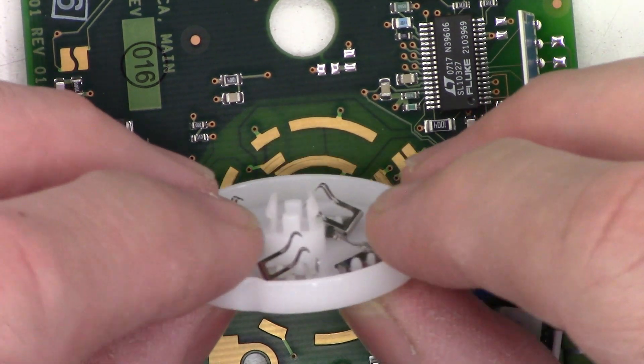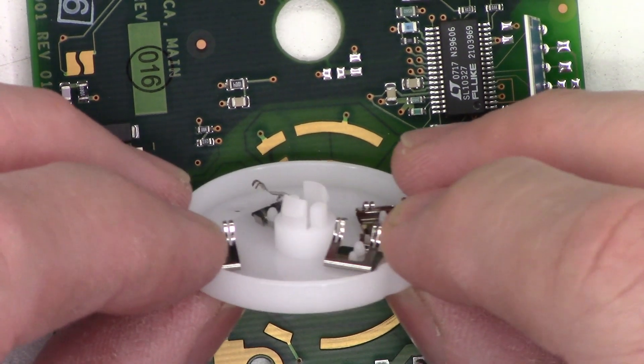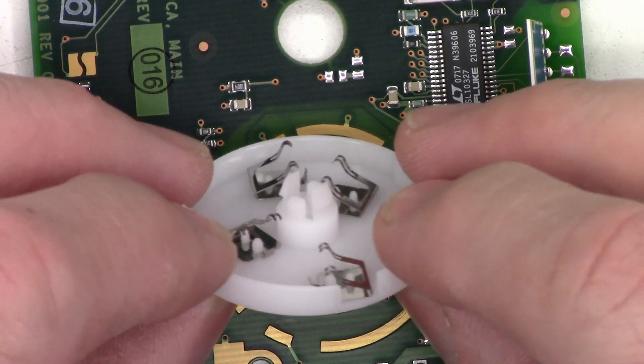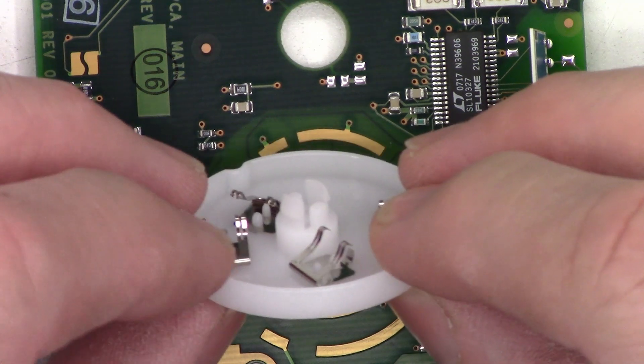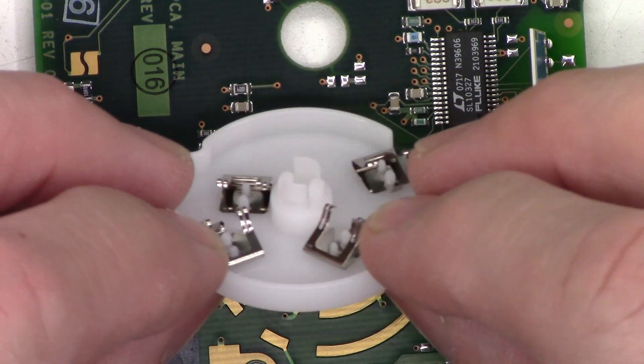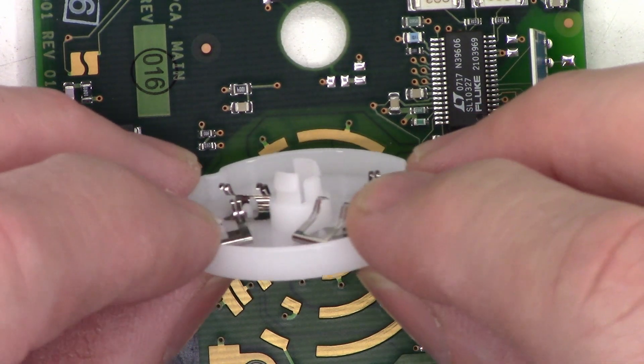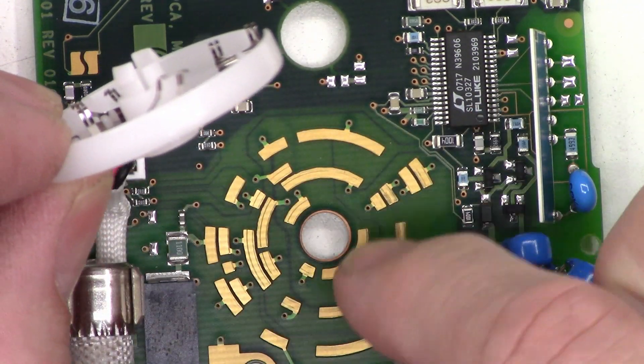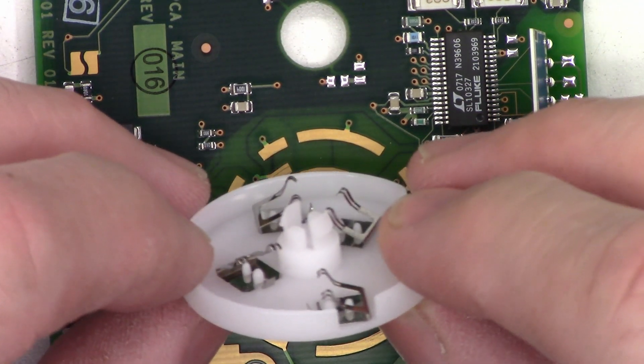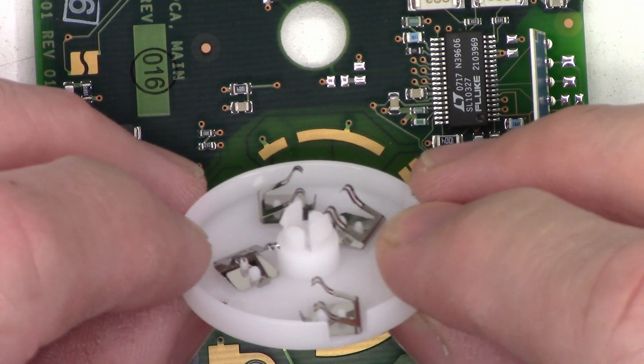I don't think I'm going to put any dielectric on there because this is completely dry at this time. These things have been known for their robustness, and I don't want it picking up grease, dirt, grime. There's no kind of a seal on here to prevent dirt and dust intrusion into here. So I'm just going to go ahead and polish the contacts up down here and we'll go ahead and clean these up, wipe them off really good, and put it back together and see if we get any different results.